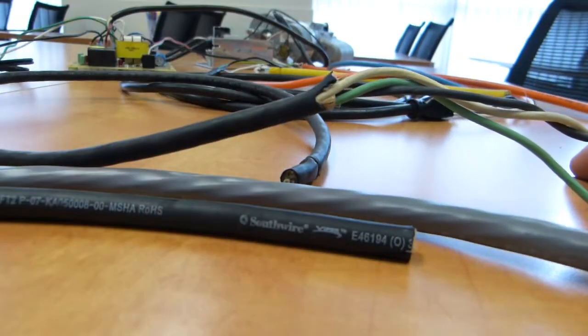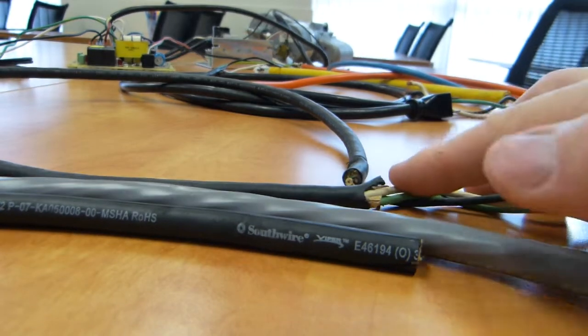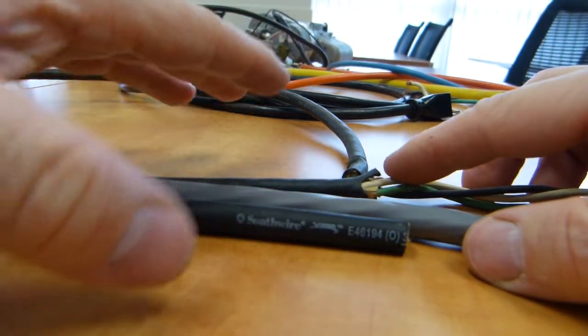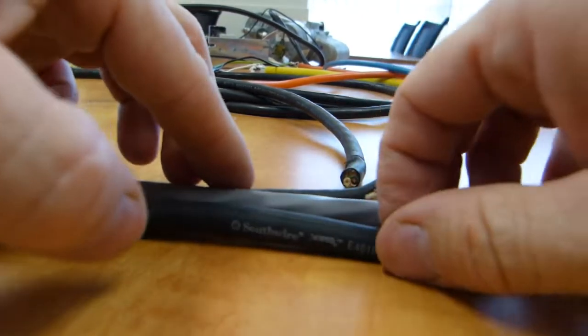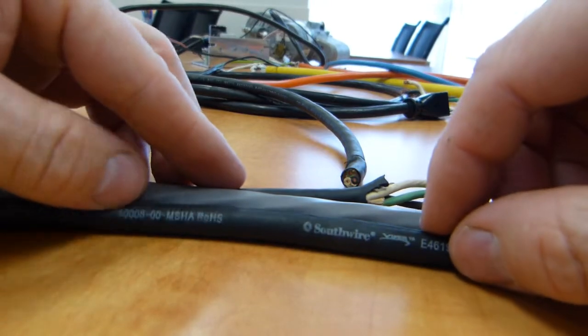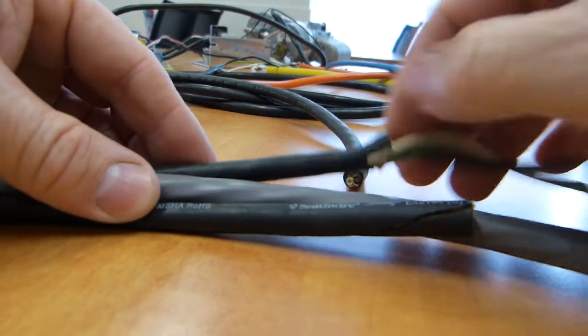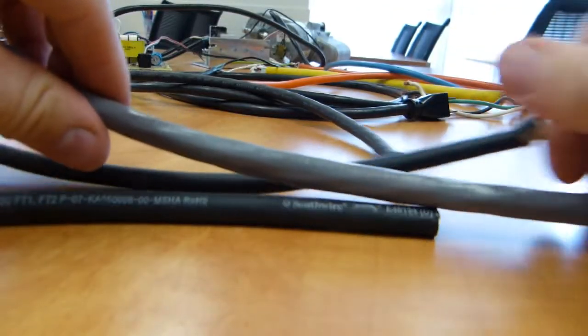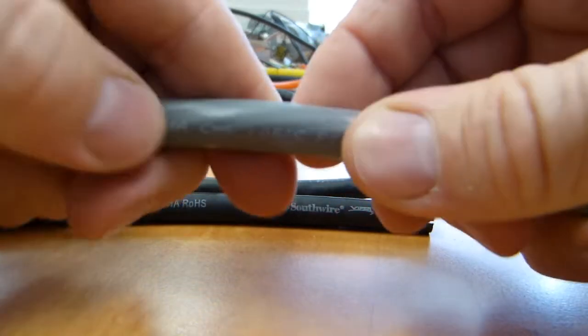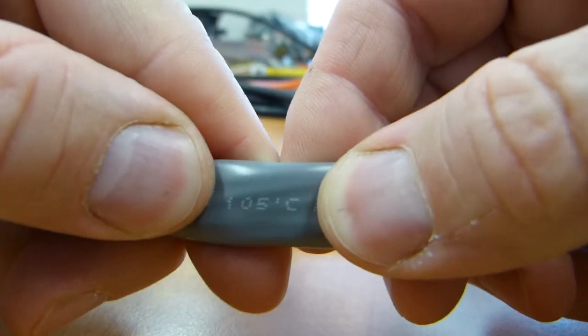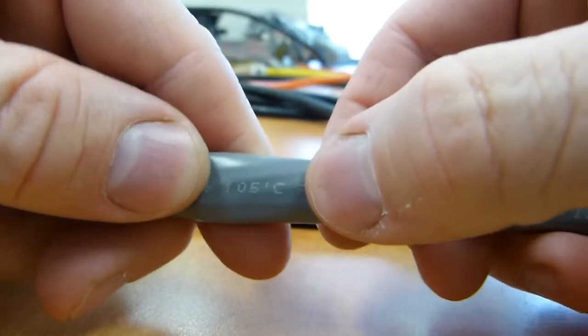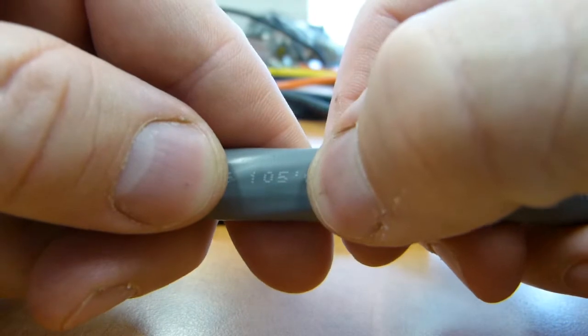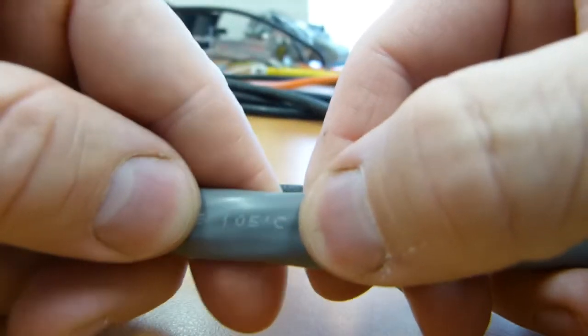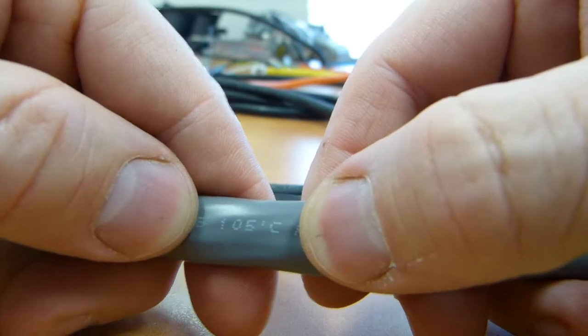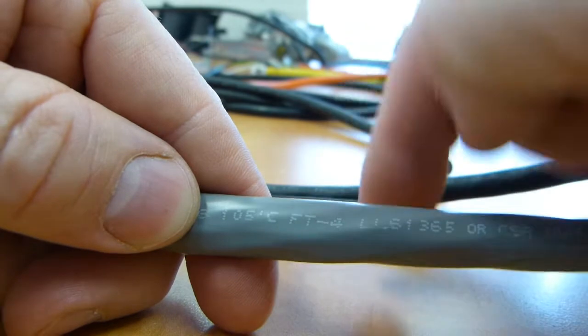you should look at both and not use a cord or a cable or any of these products outside of their intended purposes really too much. So don't be too creative with it. The amperage is just as important as the temperature rating. Now again, if you have this one here that can carry, I'm just going to invent a number for it, 40 amps at 105 degrees C, then it also means that if the temperature drops, then the amperage number can increase. So if it goes down to 90 degrees or 75 degrees, that means that this, instead of 40 amps, might be able to carry 41, 42, 45 amps. Okay, it keeps going up as the temperature goes down.